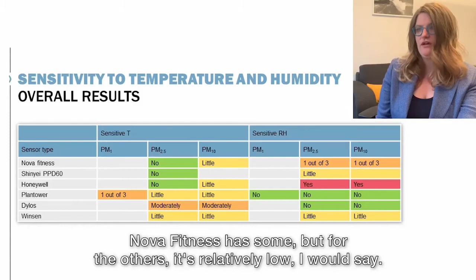So then I can go to the overall conclusions. Well, as I said, the availability is very good for almost all sensors except one Nova Fitness, and one Shinyei is also slightly lower than 90%. Linearity, also overall reasonably good, we would say. Only the Plantower is less good for PM10, and also the Winsen is not so good overall, both for PM2.5 and PM10. The accuracy, as I told you, is overall relatively low, especially for PM10. Best results are achieved by the Dylos.